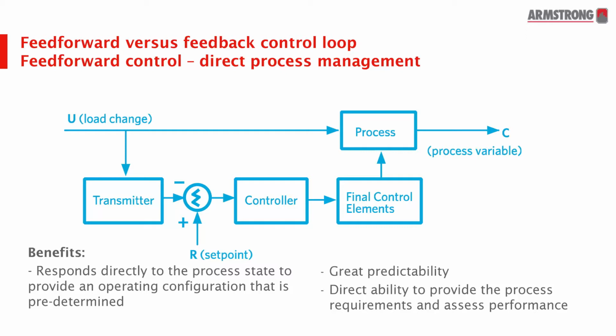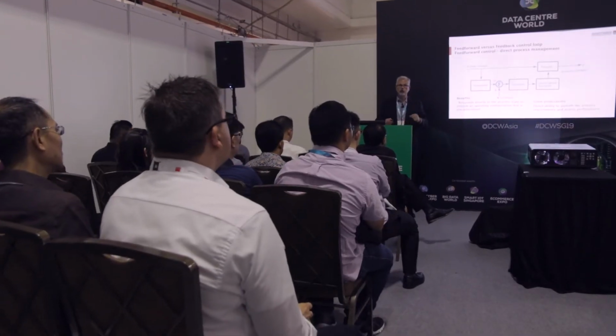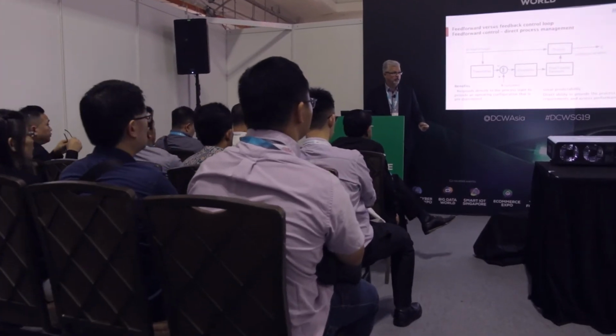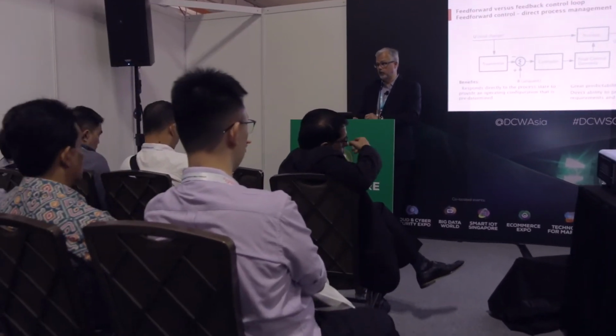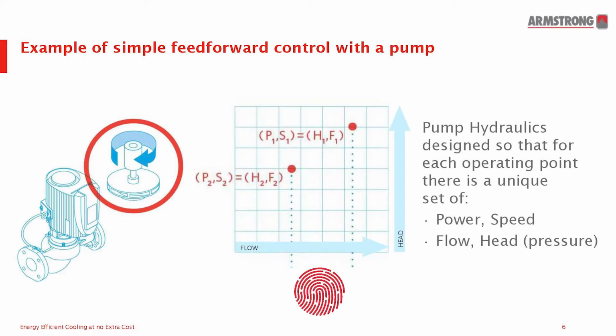And if perhaps we're not able to achieve our temperature set point with that arrangement, we've learned that something has happened. Maybe the coil has a clogged air filter and it's having a hard time getting enough air. We can adapt and we can learn that the condition of that equipment has changed and we want to change our control map, and that's a little bit of the learning process. So it's very difficult to do machine learning with feedback control loops. It's very easy to do machine learning with feed-forward control loops, where you have a predictive outcome from your original model. And that's what we've done with our automation systems.